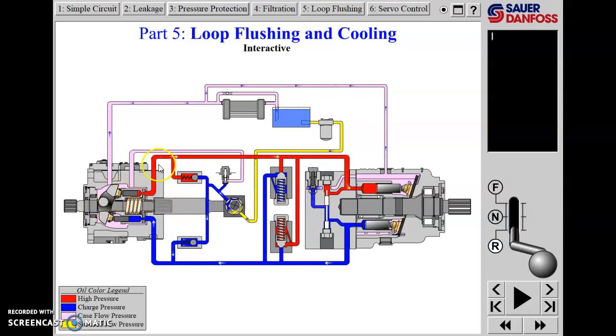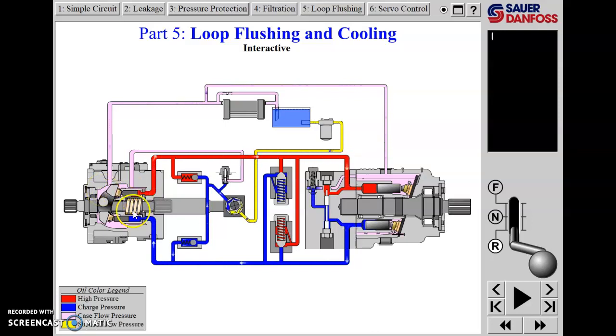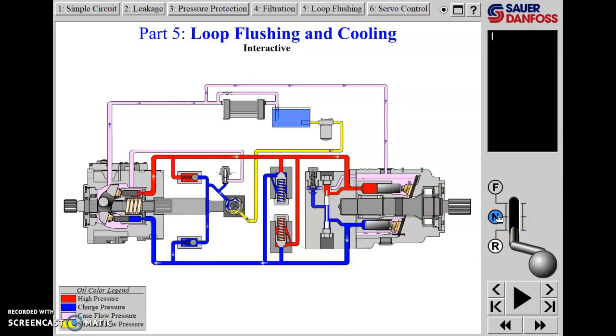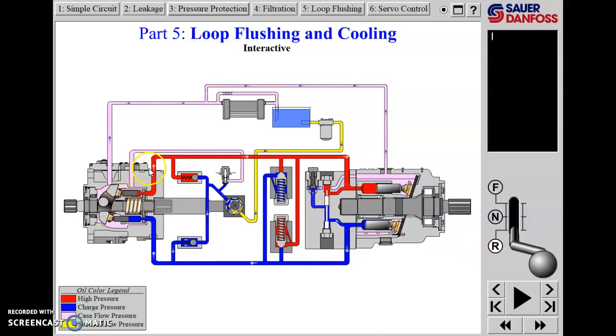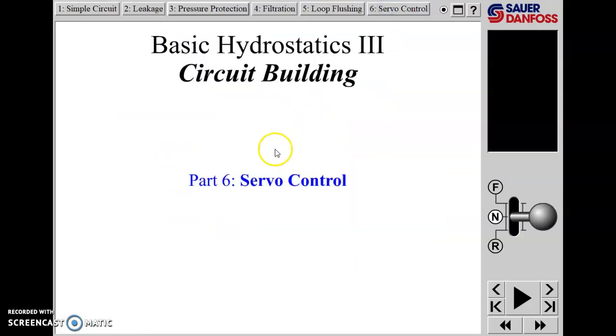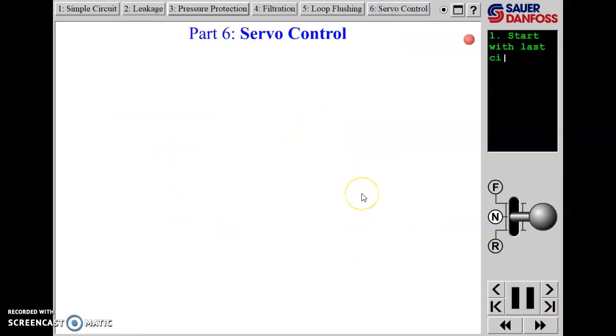The problem with mechanical linkage is that when there's pressure on the drive side of the system, that effective area pushes on the surface of the pistons in the pump, and those pistons try to push the swash plate flat. Every new piston that comes around under pressure tends to push the swash plate back toward neutral. Systems that use mechanical linkage generally need considerable mechanical advantage over the swash plate so the operator doesn't have to fight the controls when drive system pressure goes up.